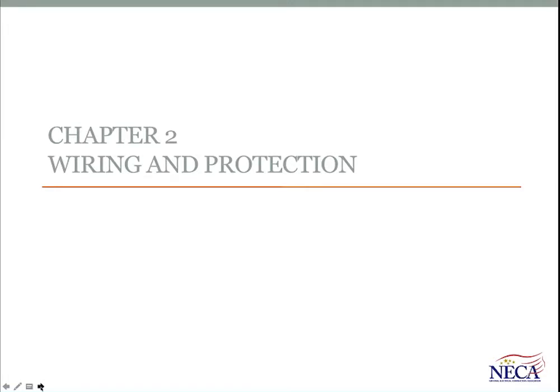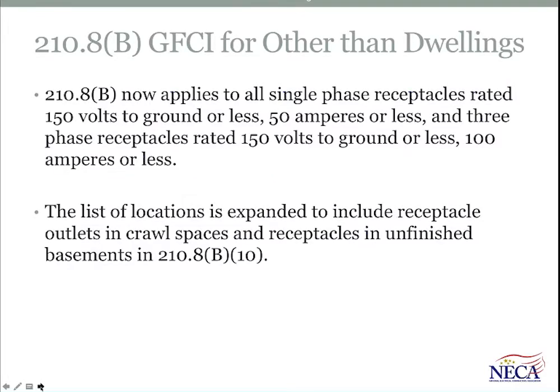Chapter 2 is titled Wiring and Protection. This is where you find a lot of your overcurrent protection, your branch circuit limitations, feeder limitations, grounding and bonding, and so forth. We'll cover a few of these changes. I think the NEC historically sees expansion of GFCI requirements for dwelling units and beyond dwelling units each time we move from cycle to cycle. And the big one there we talk about this cycle is Section 210.8(B), which applies to all single-phase receptacles rated 150 volts to ground or less and 50 amps or less, and three-phase receptacles rated 150 volts to ground or less and 100 amperes or less. These are new requirements for GFCI protection.